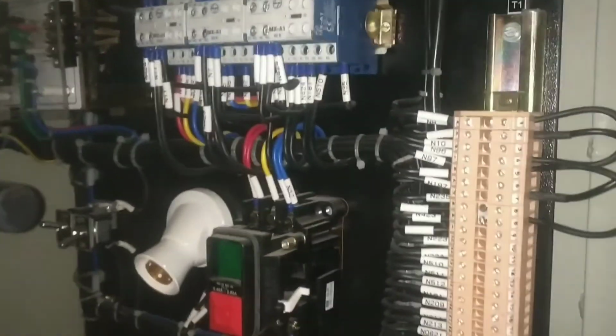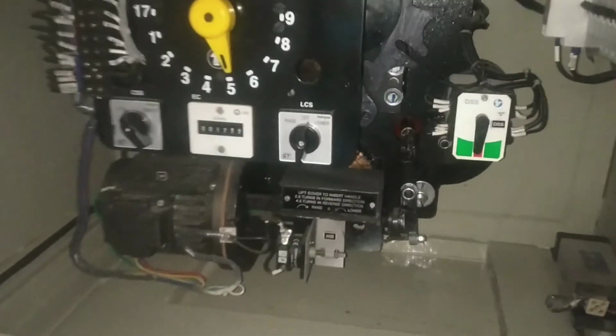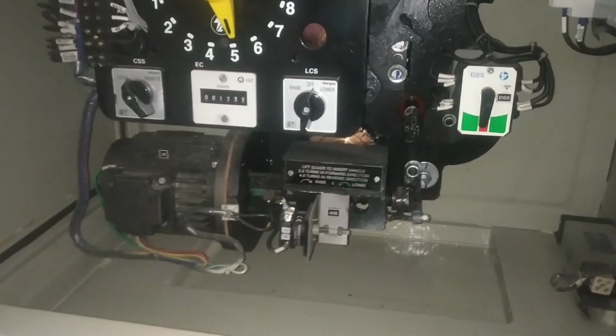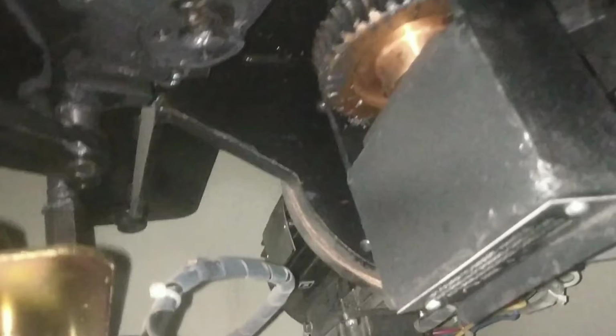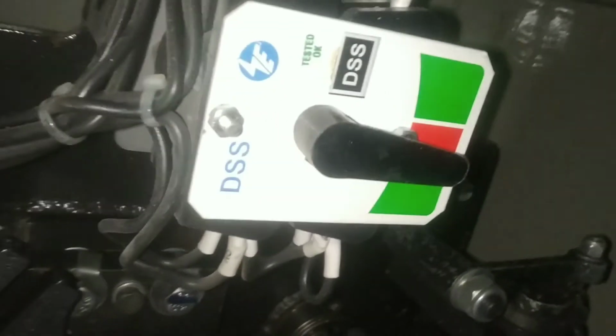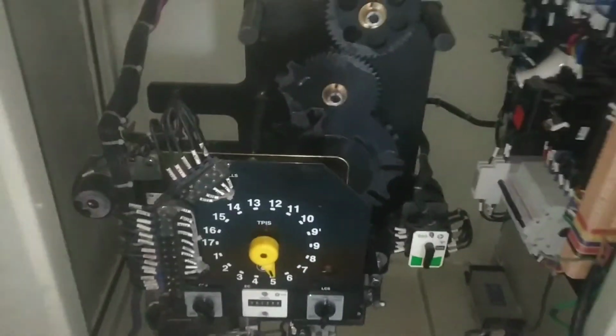Auxiliary control supply is provided by a control transformer and the auxiliary supply will be controlled by a contactor which will be switching the supply on and off as required. There is a motor also present within the OLTC which is rotating the gears and thereby changing the tap. The motor and the shafts are coupled through a gear mechanism. As you can see here, this gear mechanism helps the OLTC to achieve the desired taps as per the inputs given by the tap selector. From the selector switch, controls are given out through the control wires to select the desired tap.